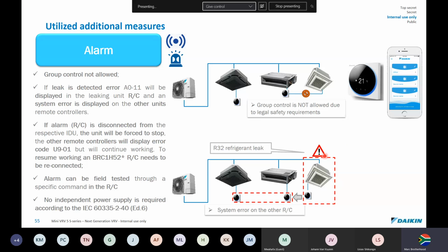If there's a leak on this system, as I was mentioning to you, there will be a system error on the other remote controls showing, hey, we've picked up a problem, but these end users won't know what the problem is. They'll just see that the air conditioner stopped. But if this is your room, you will know that the leak is in your room and it will be blinking red.